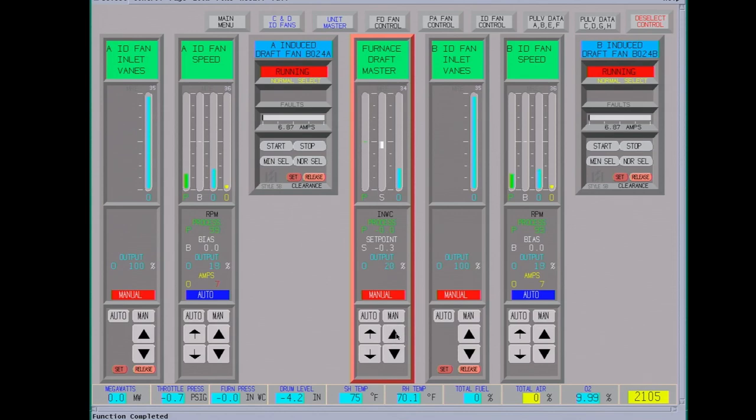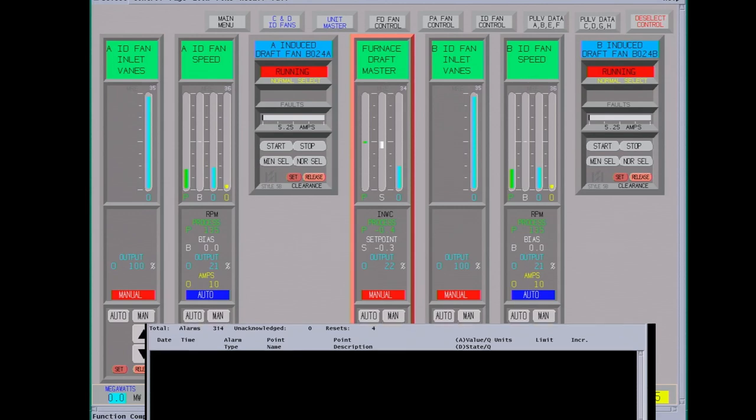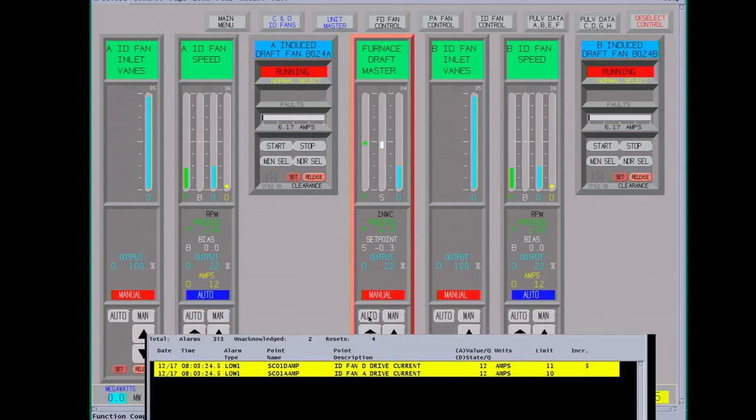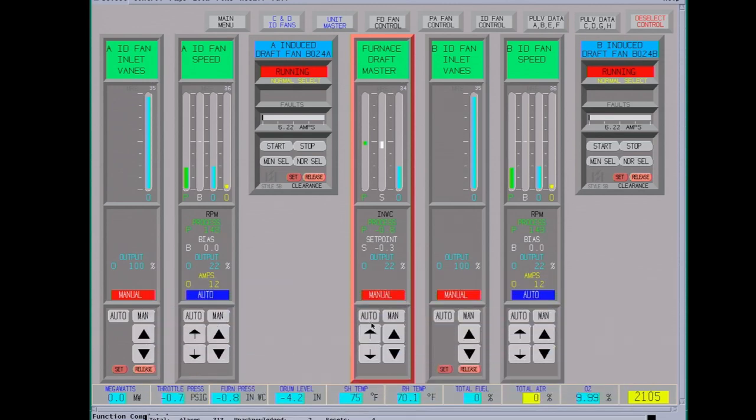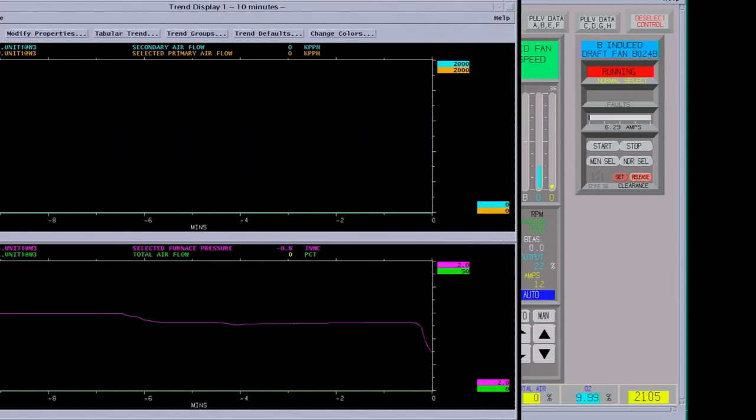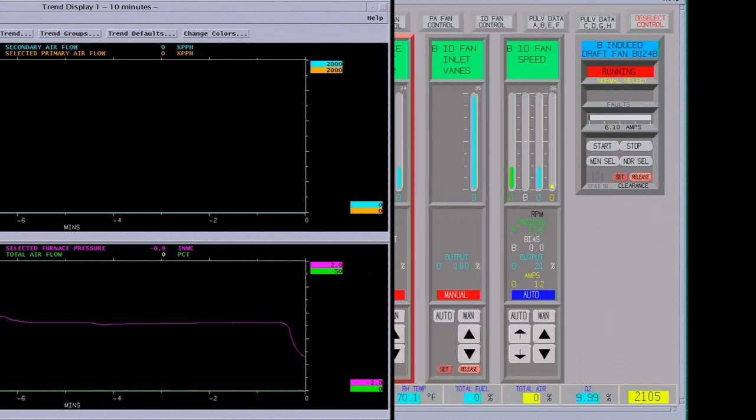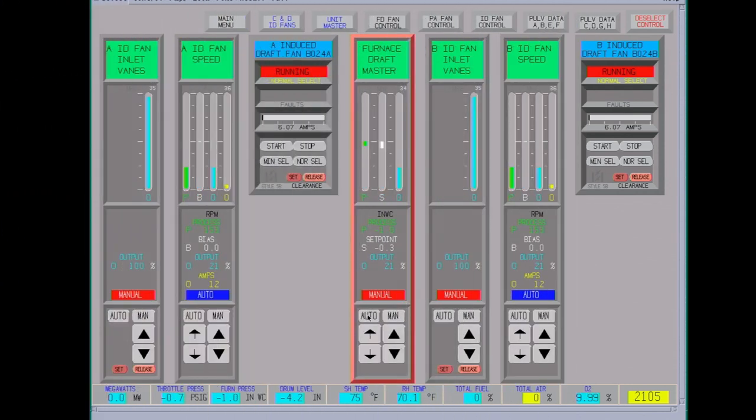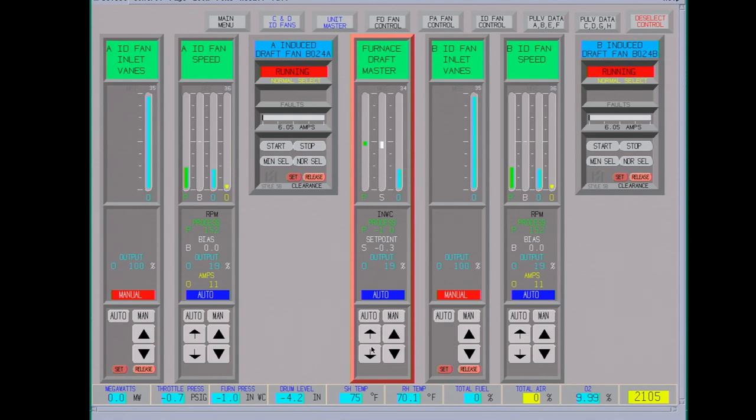We're going to bring up the fan speed just a little bit, try and get down to a negative 0.5 inches water column. Okay, we're trying to go negative. This furnace runs at negative 0.5 inches. It's pretty hard to control without much air flow going through. We don't have any of the fans running yet. We'll put this into auto, and if it doesn't control well, we'll have to take it back to manual.